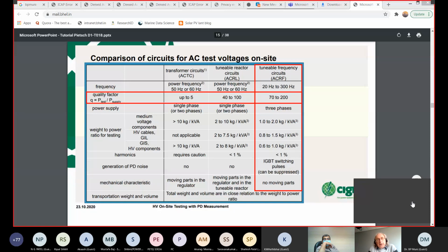If it's done, you don't even need additional equipment. You do it right now, like monitoring, and you pick up the breakdown and look at the signal traveling, because it reflects back and forth several times. By that, if it's a short cable, you can pinpoint within some meters. If it's a long cable, more than several kilometers, then plus or minus the length of the cable plus or minus 5%. In some cases better, in some cases worse, depending again on the design of the cable, the damping behavior, and so on.